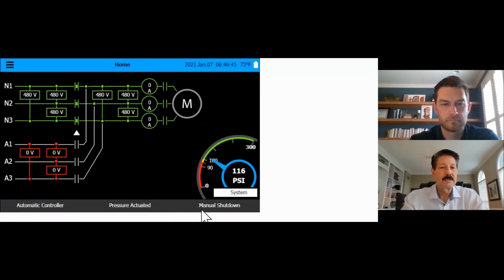Typically, everyone is shipped with manual shutdown. That's required by code. If you change it to an automatic shutdown, and we'll get into that in the near future here, you need the AHJ's approval to do that. Again, the unit itself is pretty self-explanatory.